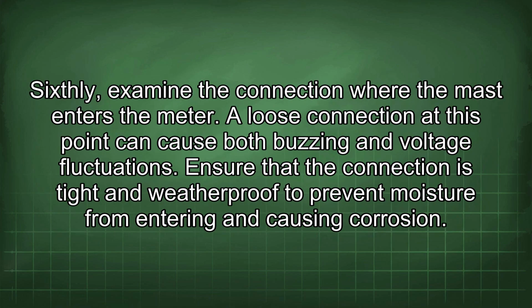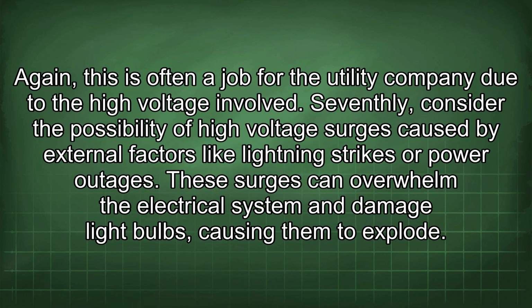Sixthly, examine the connection where the mast enters the meter. A loose connection at this point can cause both buzzing and voltage fluctuations. Ensure that the connection is tight and weatherproof to prevent moisture from entering and causing corrosion. Again, this is often a job for the utility company due to the high voltage involved.